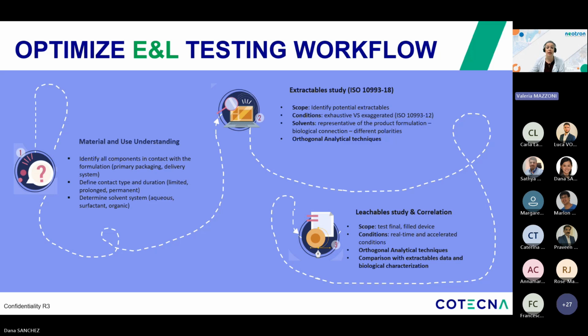The second pillar is the extractable study itself, where we apply controlled, exaggerated or exhaustive conditions according to both ISO 10993 part 18 and 12 to reveal the full chemical profile of what the materials are capable of releasing. This defines the worst-case scenario and guides method development for targeted leachable testing, which represents the third pillar. The leachable study is performed under simulated or real-time use conditions.